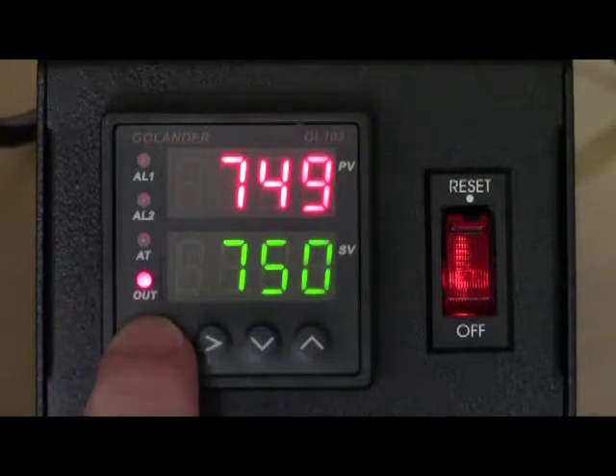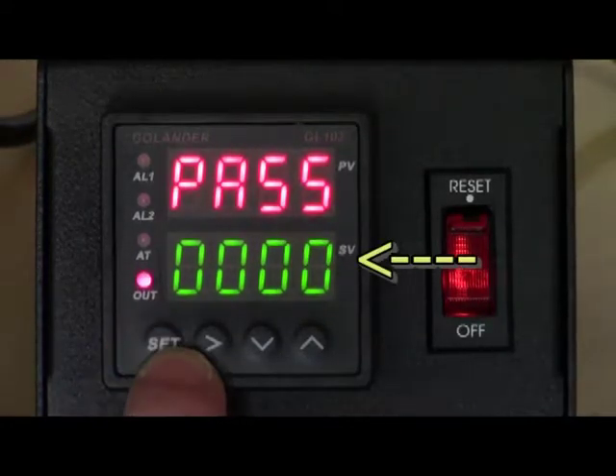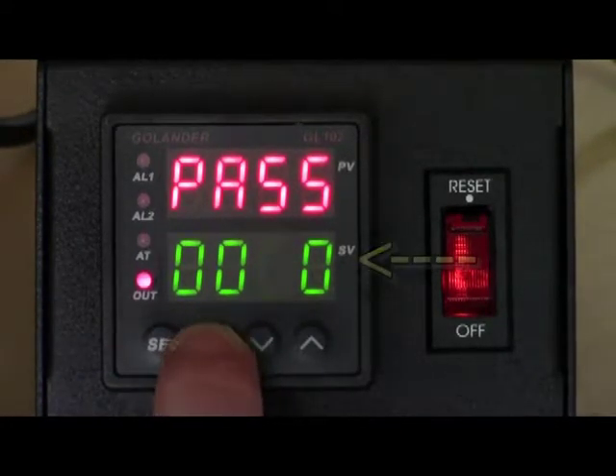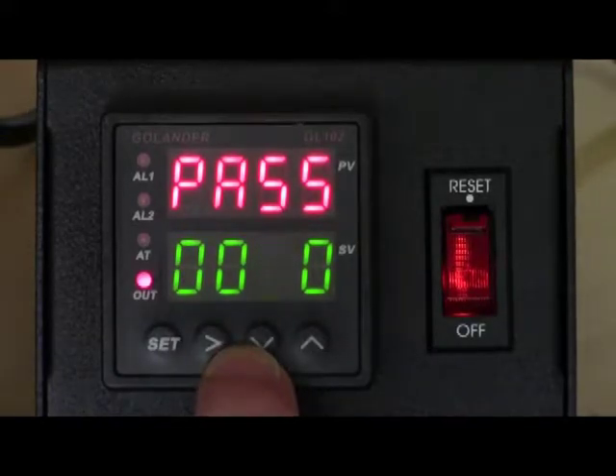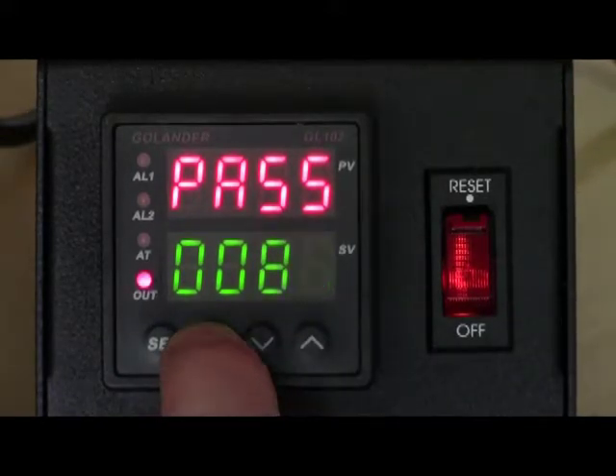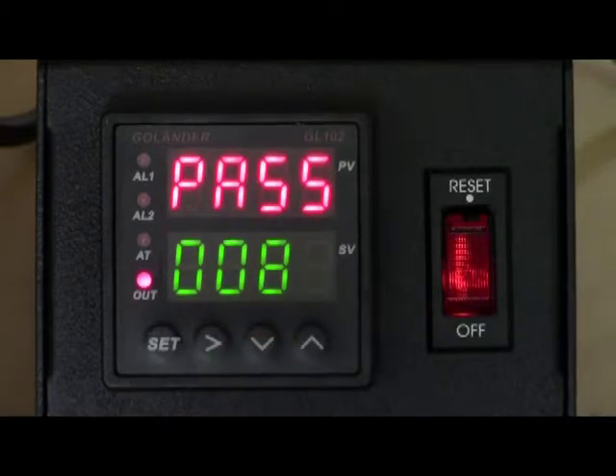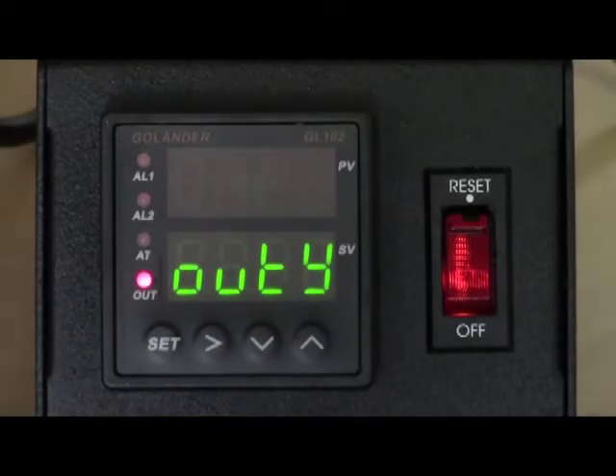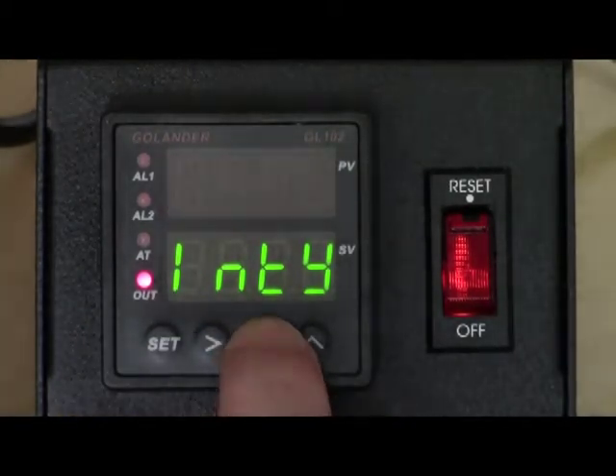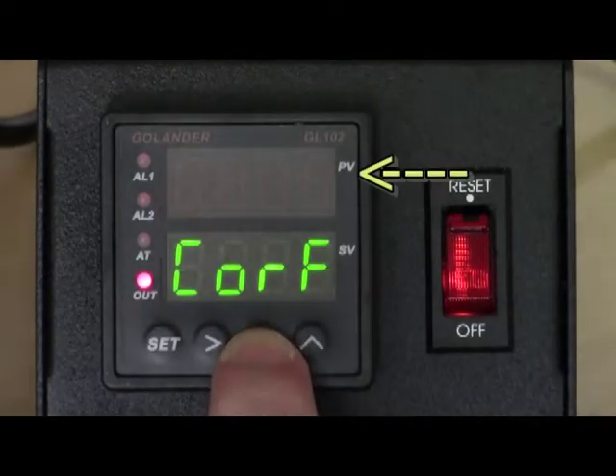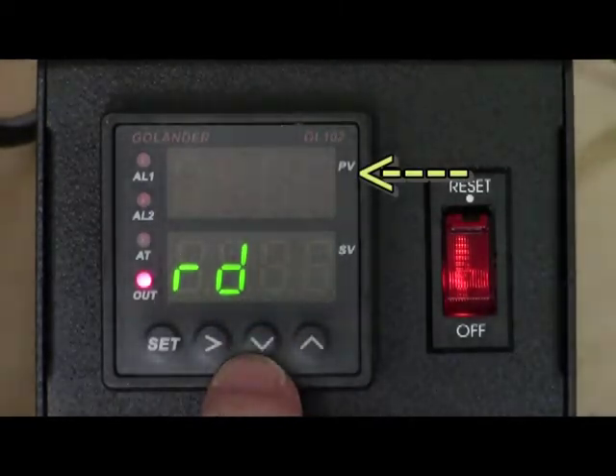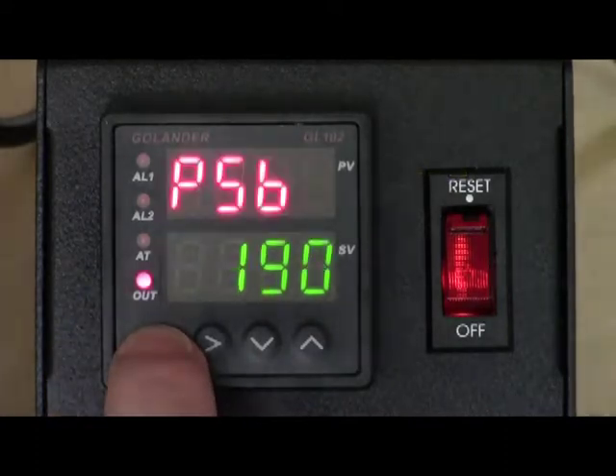To begin, press and hold the set button until the SV display reads 4 zeros with the first zero blinking. Now, using the arrow buttons, change the digital display reading to 0089 and enter this number using the set button. Using the up and down arrow buttons, change the operating parameters in the PV field until PSB is flashing and enter using the set button.